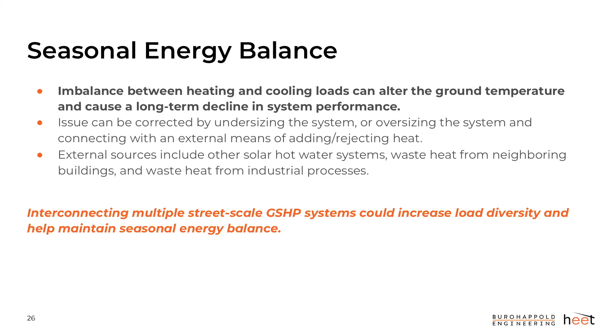For a standalone system, there's not much you can do—you can find other heat sources to balance it out. But with this GeoMicroDistrict model, because the systems are interconnected, you have more opportunities to increase diversity. Some buildings may use more heating, others more cooling, which evens everything out and lets the system operate much more efficiently.